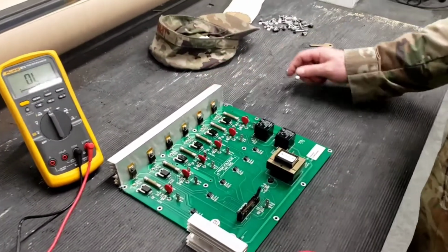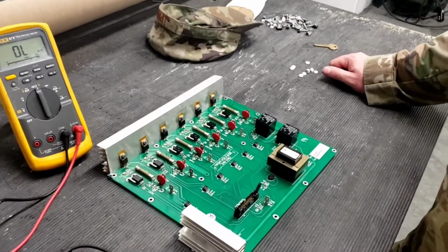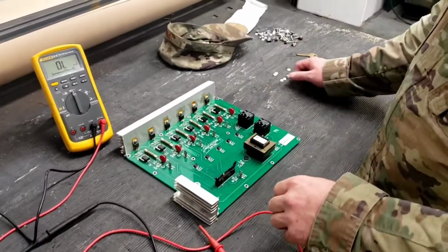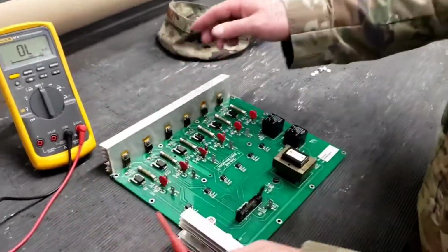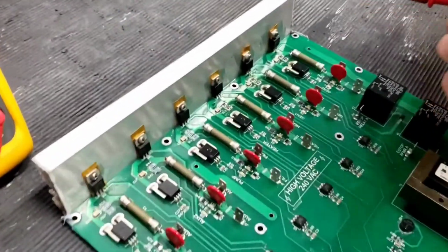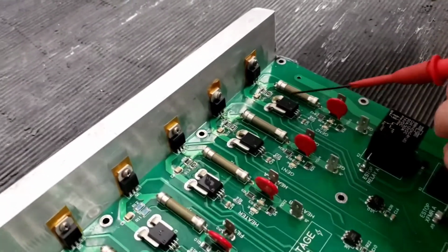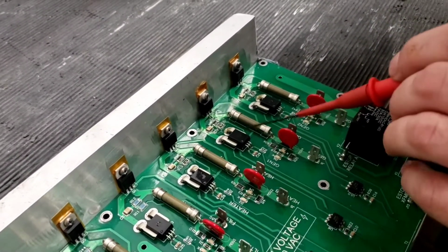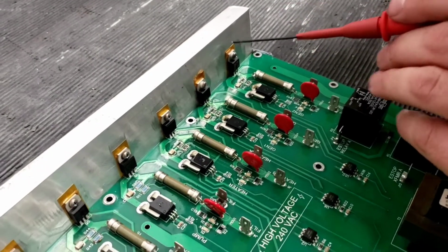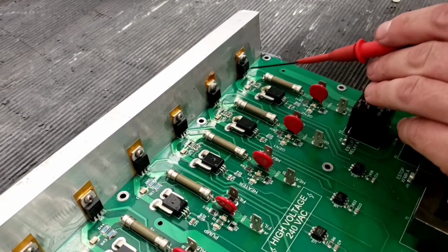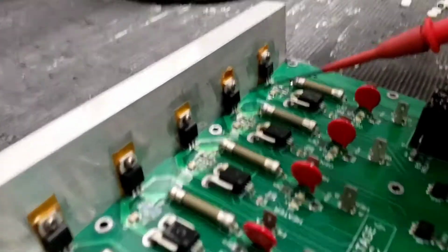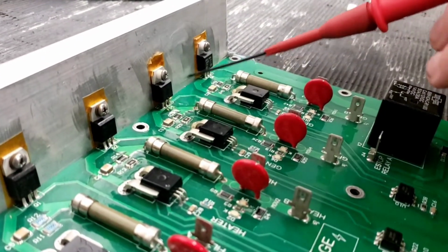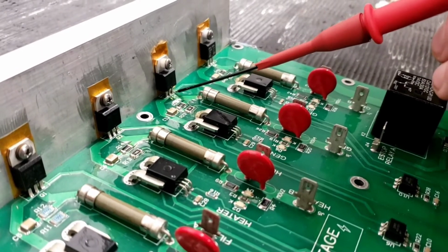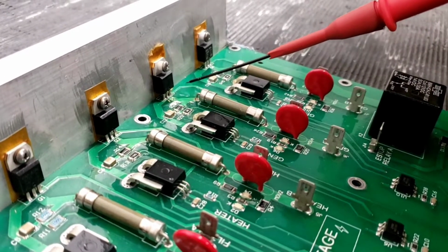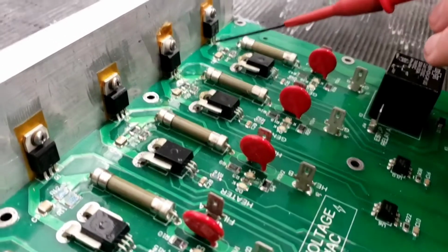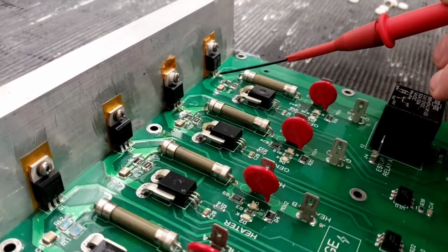All right, so the test we did on the circuit board was in the machine, but we can't film when it's in the machine. So just to show you some of what we did, you'll have to imagine this. This is Gen 2, which is the good circuit. This is Gen 1, which is the bad circuit from all the previous footage we just showed you. These are the transistors that are controlling that. When we first came out here, we got 120, 120, 120, and then on this one, we had 120, 96, and 120.